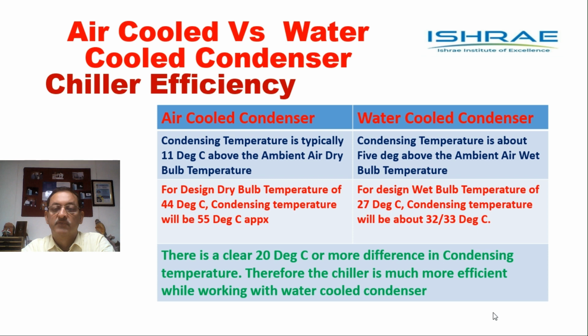And this I'm talking just with respect to the design wet bulb temperature. In summer condition, when the dry bulb temperature is of the order of 44 degrees centigrade, wet bulb temperature at that particular condition will be much lower, around 22 or 23 degrees centigrade in Delhi. So the condensing temperature will be much lower. And we can see that there is a clear 20 degrees centigrade or more difference in the condensing temperature. And we know that a chiller is more efficient when the condensing temperature is less, and it becomes less efficient when the condensing temperature goes up. And therefore, the chiller, while working with the water cooled condenser, is much more efficient.